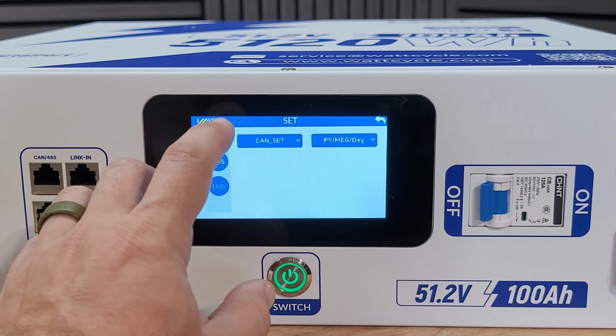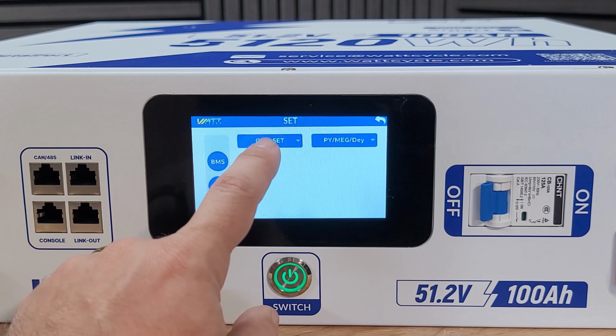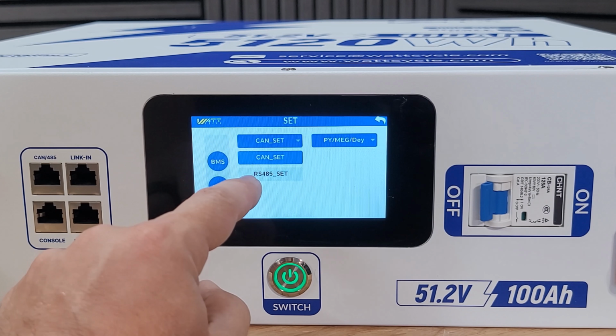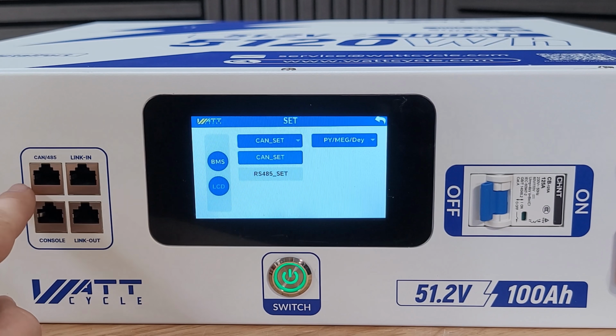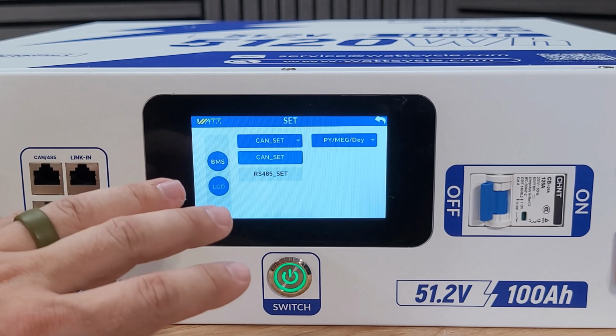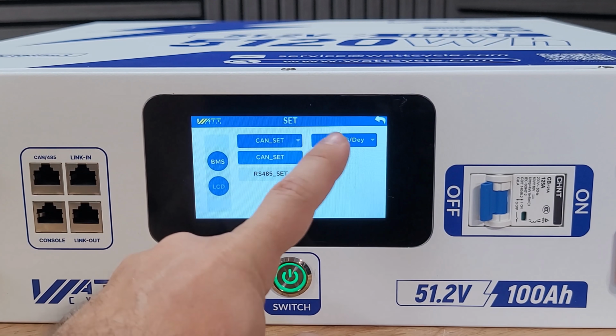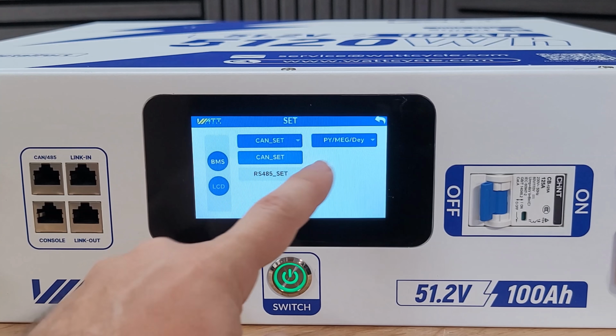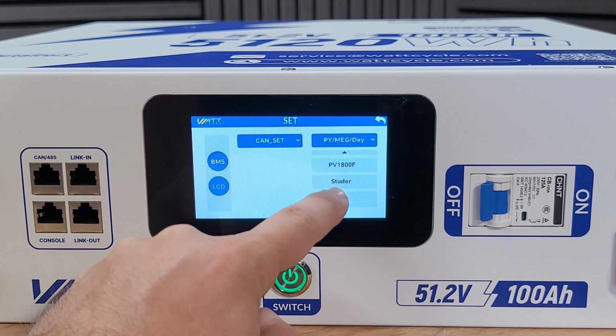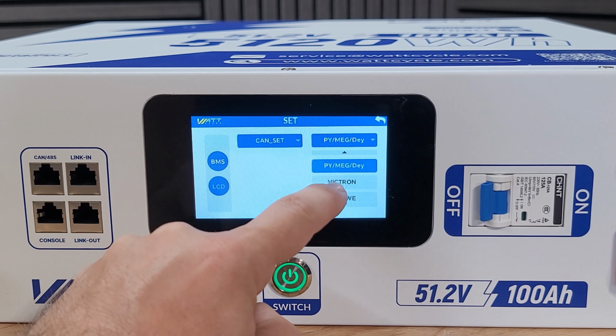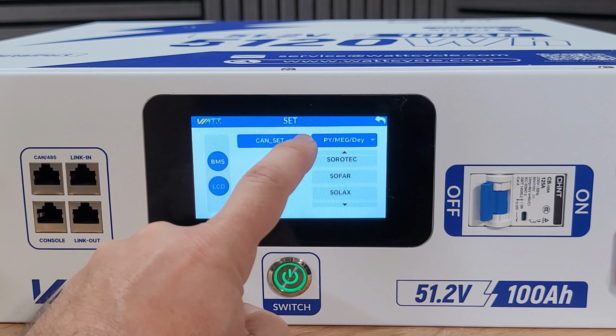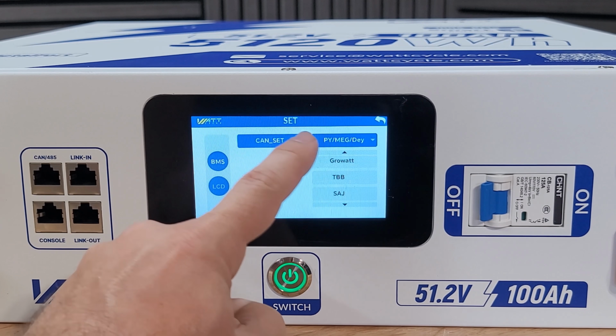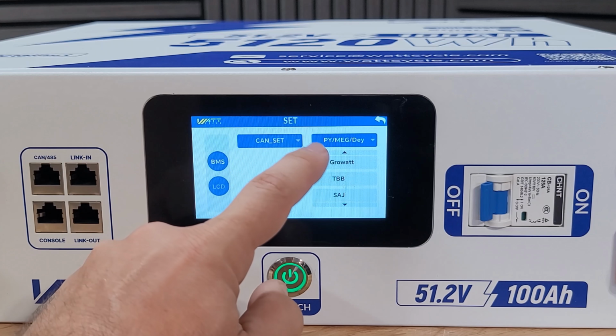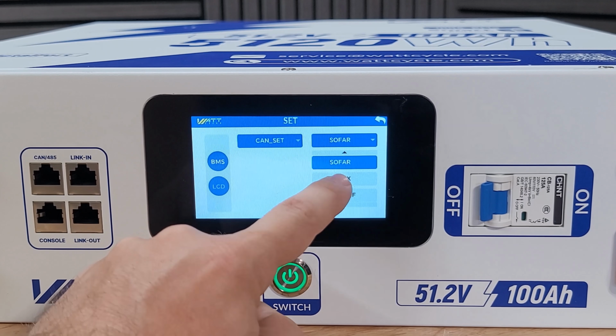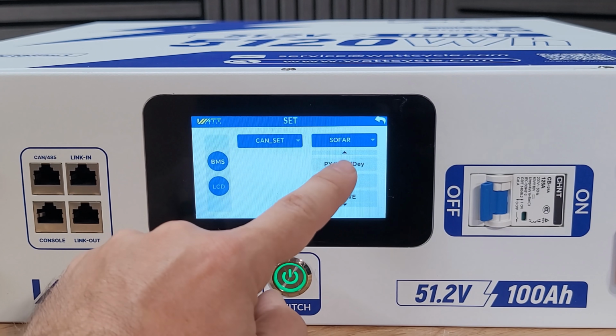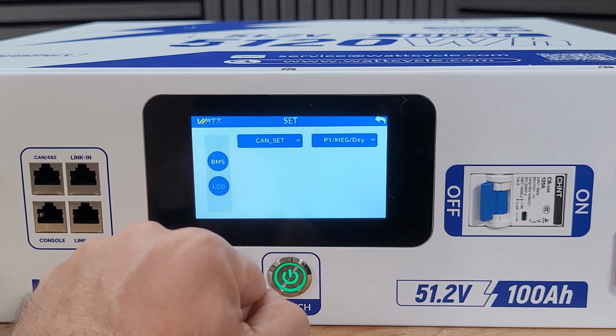This is one of the most important pages here, setting your communication. You can do both CAN and RS-485, which are these Ethernet ports over here, so you can use this with pretty much any inverter on the market. Pylon is one of the most common ones, as well as Lux. But that's one thing I noticed here, is there isn't a Lux setting, which is the most common for EG4 inverters, which are the ones I recommend. Luckily, EG4 inverters can work with Pylon, so I've been using it on that setting.